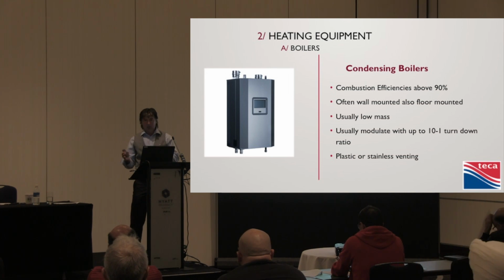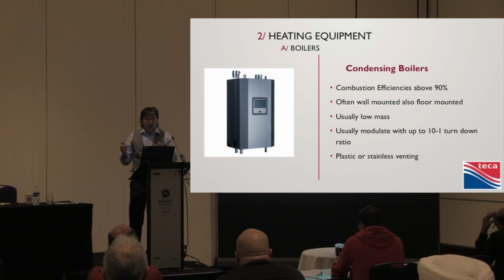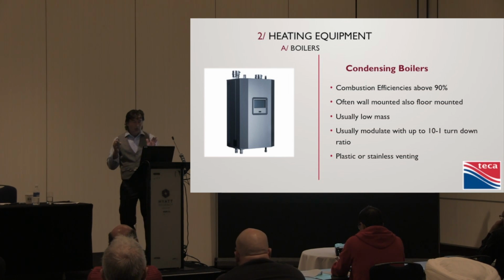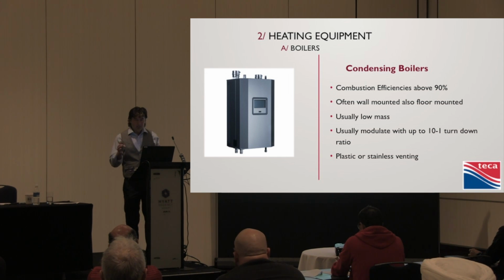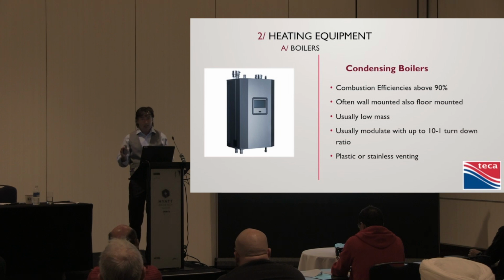So let's say your load is 100,000 BTUs. Okay, I've got 100,000 BTU boilers. But our design time, how often are we actually at 100,000? Well, if your load is 100,000, it's 90% efficient, so our boiler would be 110,000 input because it's 90% efficient. So our output is 100,000. If our requirement of our heat load is 100,000, our output of our boiler, not our input, but our output of our boiler is going to be 100,000. So that's all great. So we address the coldest day of the year, which happens every couple of years. That's the way we sized our boiler.